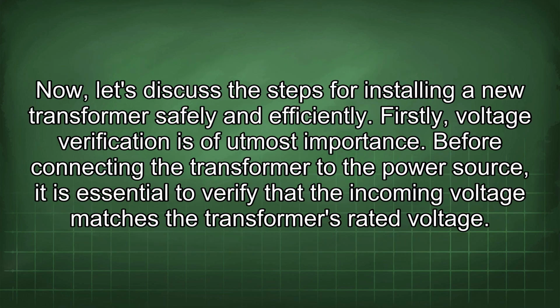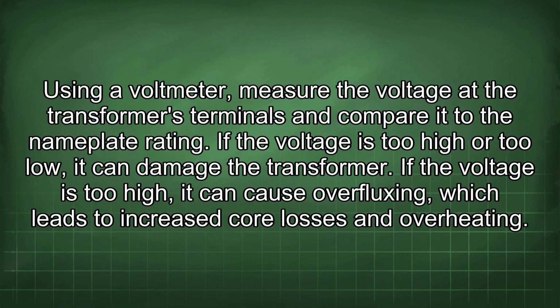Now, let's discuss the steps for installing a new transformer safely and efficiently. Firstly, voltage verification is of utmost importance. Before connecting the transformer to the power source, it is essential to verify that the incoming voltage matches the transformer's rated voltage. Using a voltmeter, measure the voltage at the transformer's terminals and compare it to the nameplate rating. If the voltage is too high or too low, it can damage the transformer.